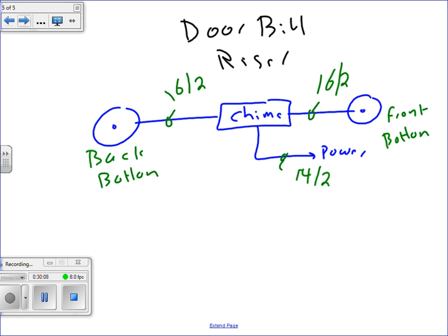By the way, when it comes to low voltage systems, class 2 and 3 circuits, guys, you can use 18, you can use 22. Does anybody know the difference between using 18/2 or 18 or 16/2? Voltage drop on the circuit and the length. The longer the circuit, the further the distance, the more you use 16, the bigger the conductor, right? So for phone lines, 22 is good because we don't have a whole lot of amps coming out of it, just signal.